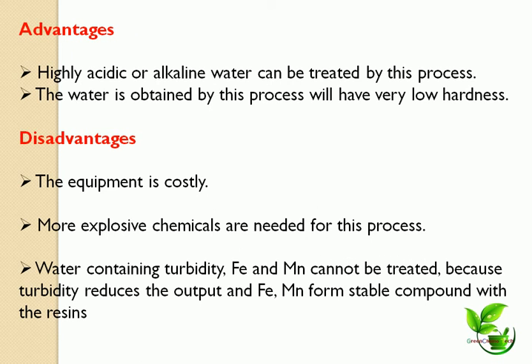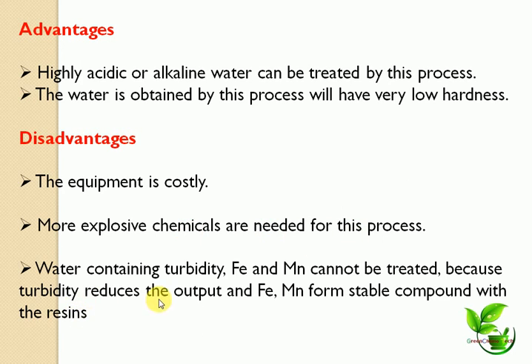Advantages of the demineralization process: highly acidic and alkaline water can be treated, and the water obtained has very low hardness. Disadvantages: the equipment is very costly with high capital investment; more expensive chemicals are needed; and water containing turbidity, iron, and manganese cannot be treated, because turbidity reduces output and iron and manganese form stable compounds with the resins.